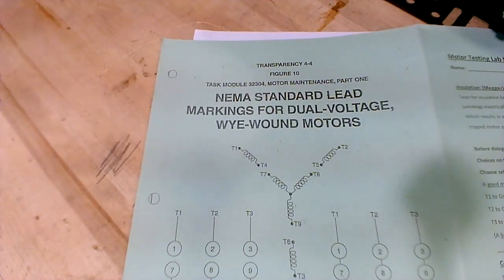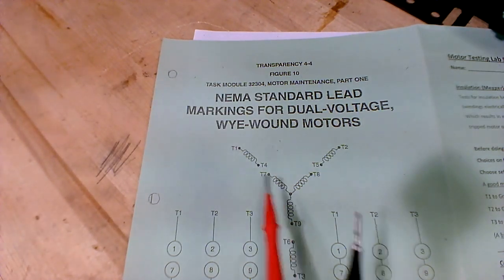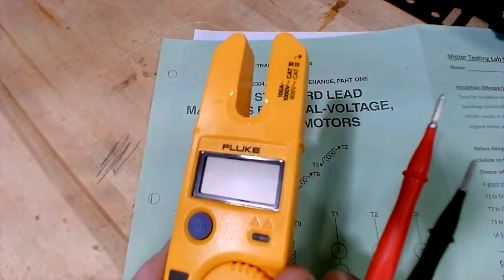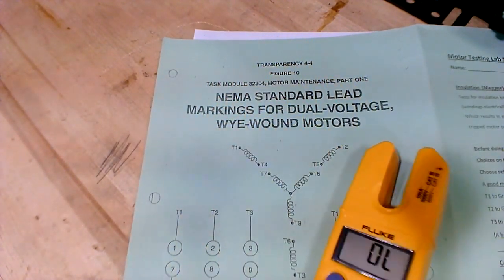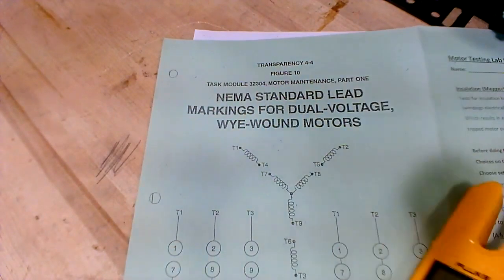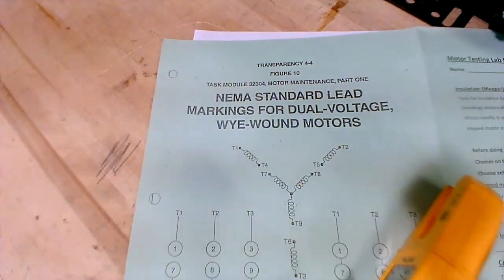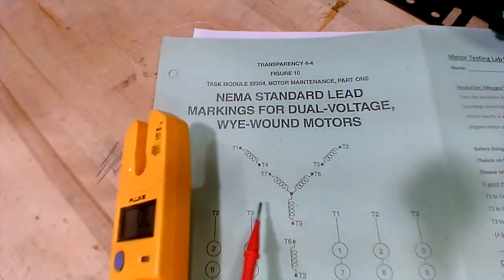We take our meter. Where's the meter at? Your next test would be checking continuity through the winding. So you would simply put the meter on like that, and you're just going to go up here, and you're not going to check the ground, but you're going to check through the motor.